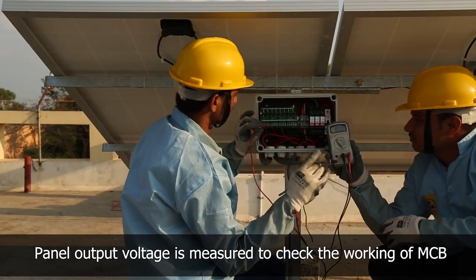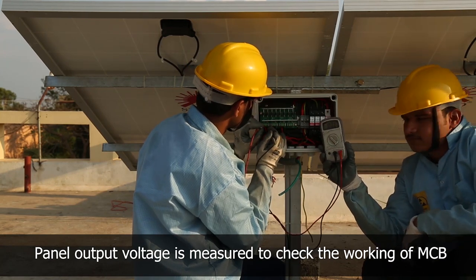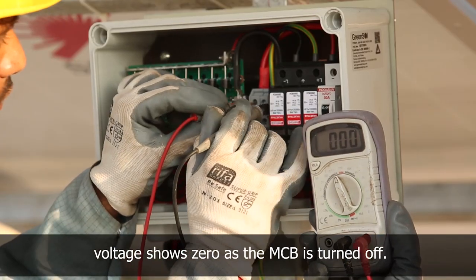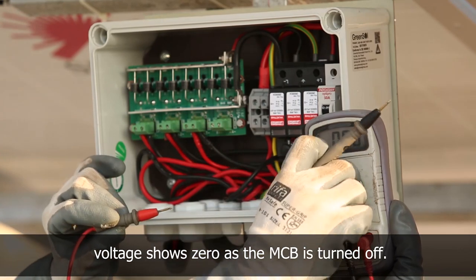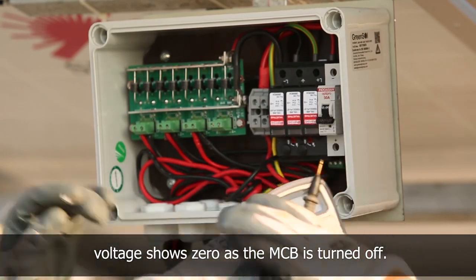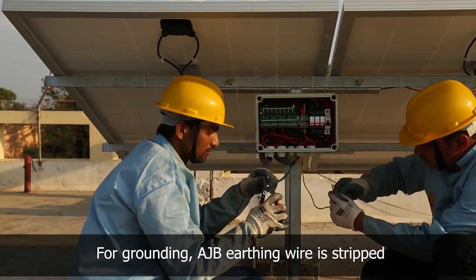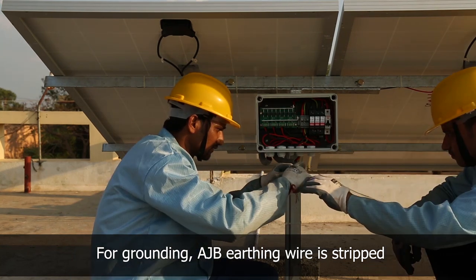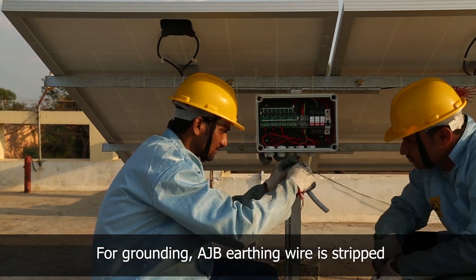Use a multimeter to check the output voltage of the panel. Ensure that the reading shows zero as the miniature circuit breaker is turned off. This shall confirm that the miniature circuit breaker is in working condition.